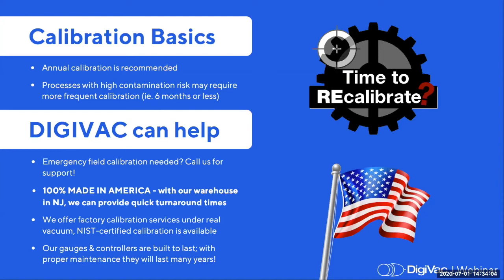We realize that sometimes it's impractical to remove a gauge from service and send it to us in order for calibration. So in that event, if you need emergency field calibration, you can feel free to call us for support. We have several field calibration processes that will help to keep your gauge online if you don't have the time to send it back, and we can always assist with that. Our warehouse is in New Jersey, and we provide extremely quick turnaround times. Our calibration and repair backlog is typically less than a week from receipt, and we can always expedite on request.